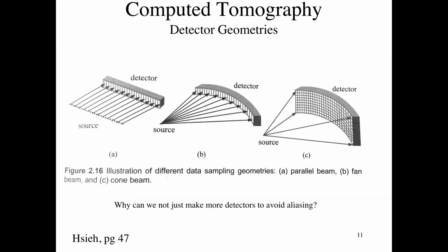They have an array of detectors that, when we shine the X-ray through the patient, we sample on this array, right? So we get discrete estimates of the X-ray fluence across the integral of that square in that array. In early CT, when they used to do one slice at a time, they would have a single detector row element, and say there's 512 detectors across that element. And that single row would capture samples through the patient, right?